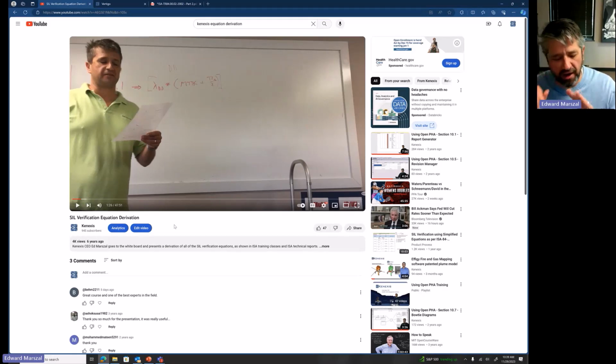But I derived every equation that's used in the Kenexis Vertigo software, which is essentially the same as the equations used in the ISA training class, and pretty much everybody else's software should be using them. Don't get me started on the Markov model stuff. I'll suffice it to say that the equations you're looking at are analytical solution equations, and a Markov model is only a numerical approximation. So why would you use a numerical approximation when you can use an analytical solution? Marketing is the answer. I digress.